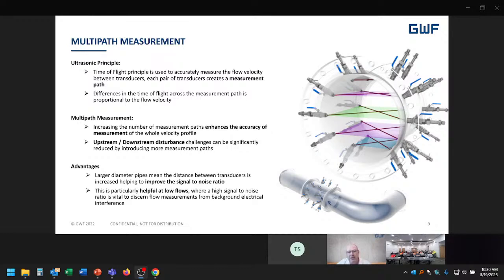Again, by having more and more measurements in there, we can deal with very tight upstream and downstream conditions by being able to average the flow going through the system. By having more transducers, and also as the pipe gets larger, we get a better signal to noise ratio, because we have a longer distance between the sensors, which means we can be more accurate over a wider range, especially where low flows are required. We can ignore background interference by having good signal to noise performance.